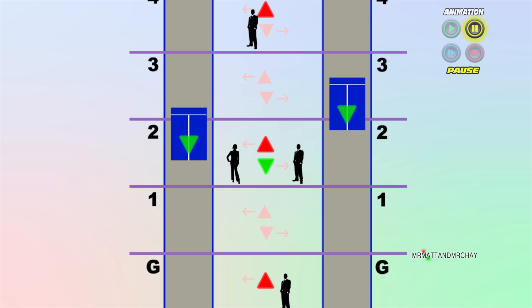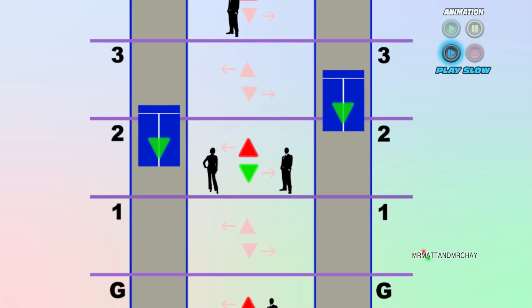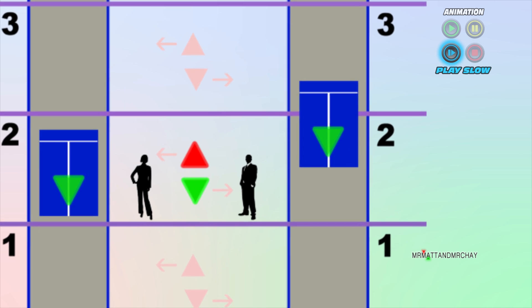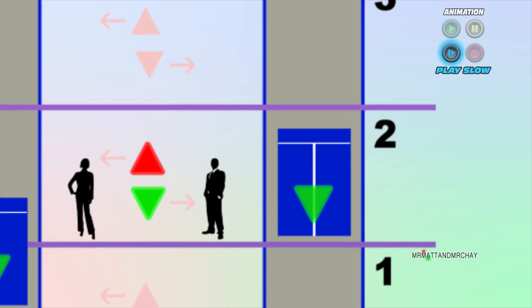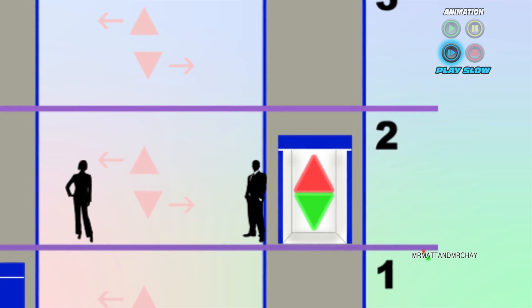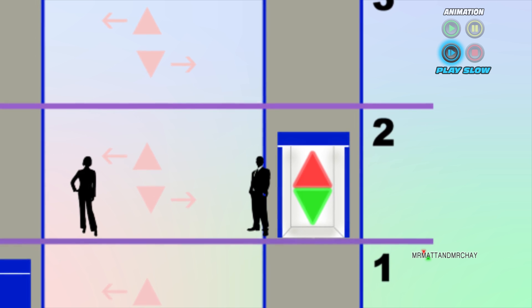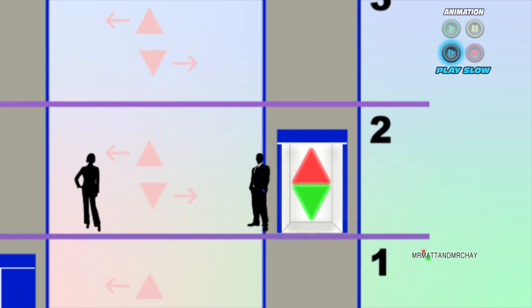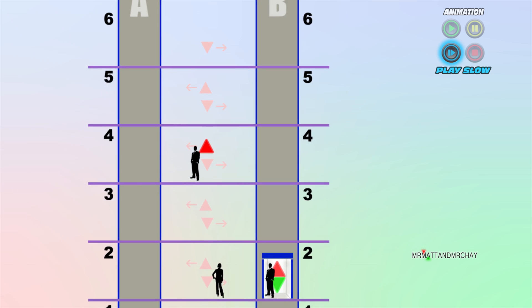As explained in part one, when an Otis lift gets to its destination, it doesn't care in which direction it goes next. This means that both up and down landing calls are cancelled at the same time. Two people enter, but the person going up gets into the car first, which gives the lift its direction.